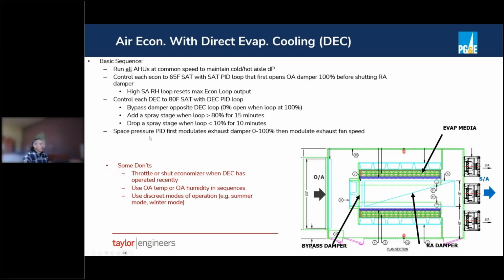The other important thing with an air economizing system is you need to have some way to control your exhaust. That's usually off of a space pressure PID loop that first modulates the exhaust damper open and then modulates the exhaust fan speed. We aren't showing the exhaust as part of this air handler because the exhaust fan can be separate from the air handler. But you need some way to measure the space pressure and then modulate your damper. Often you can just open the damper and not even turn on the fan. But when you're bringing in lots of outside air, then eventually you'll need to modulate the fan as well.